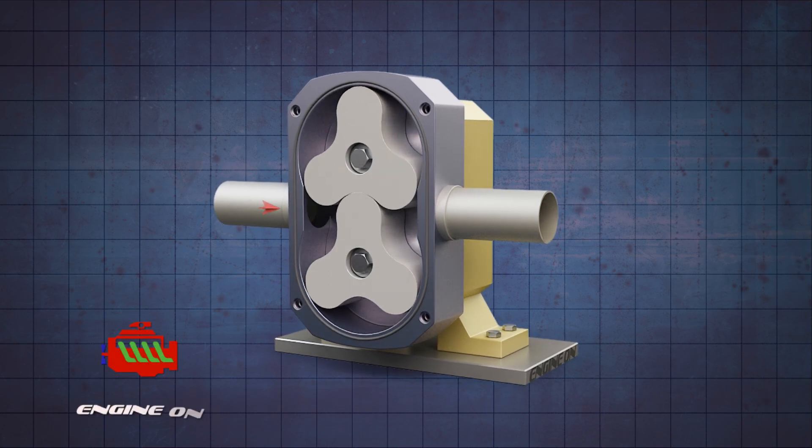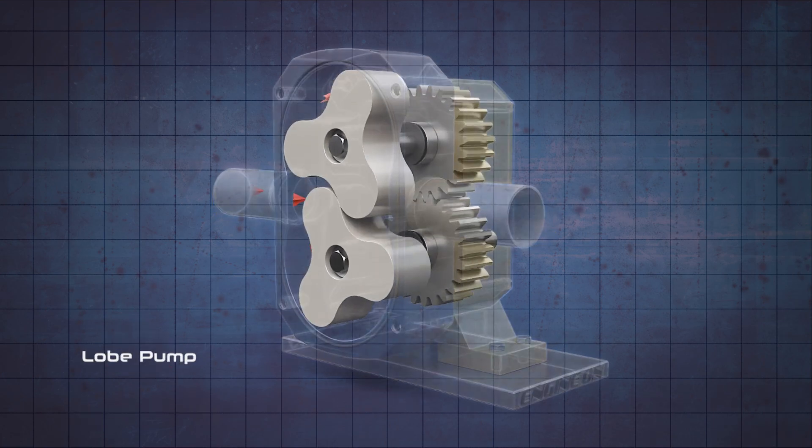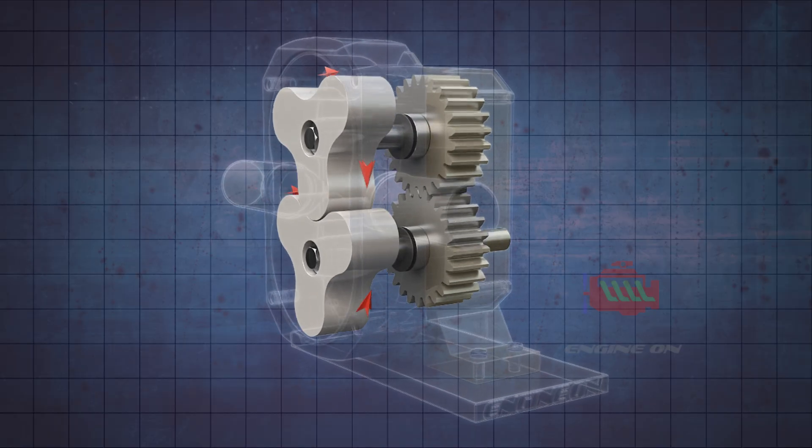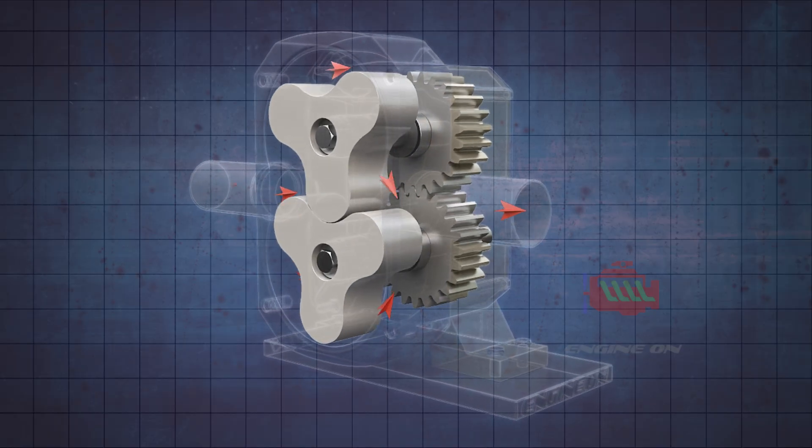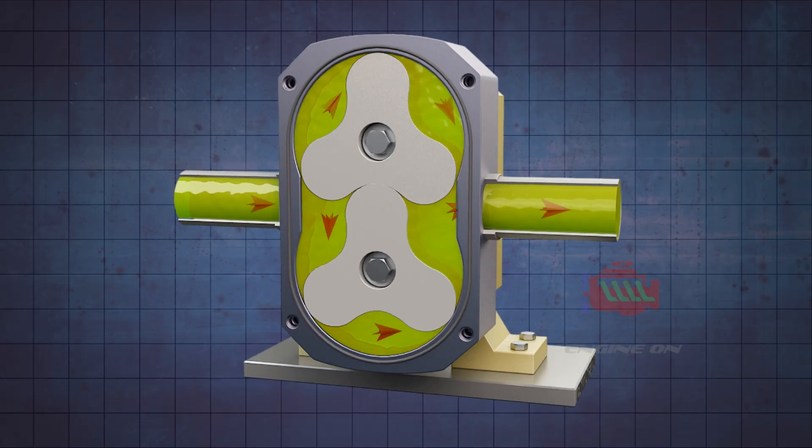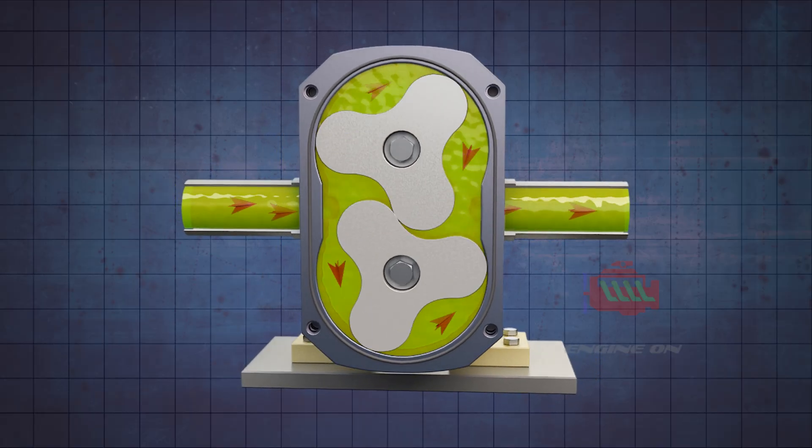A lobe pump is a type of positive displacement pump where two or more lobed rotors rotate in synchronization without contacting each other. The rotating lobes trap and transfer fluid from the pump inlet to the outlet.